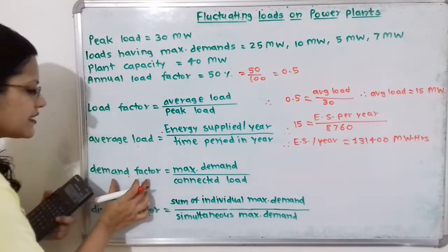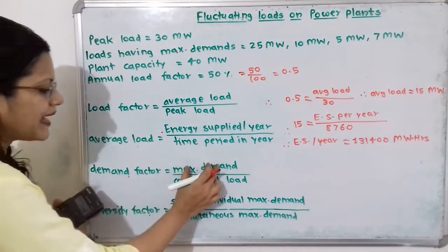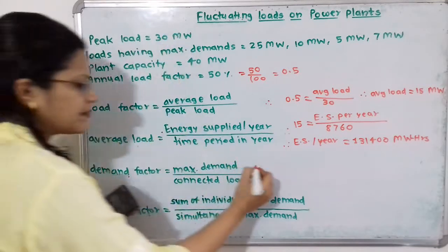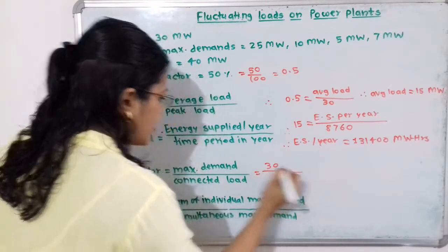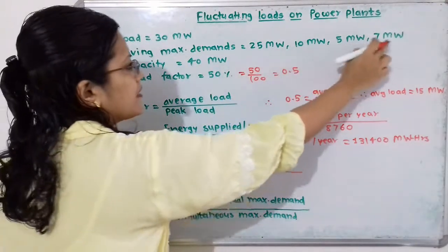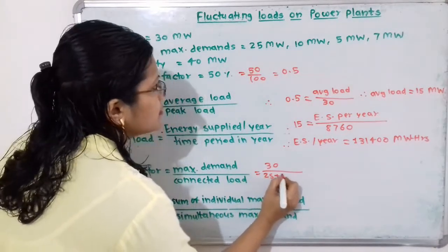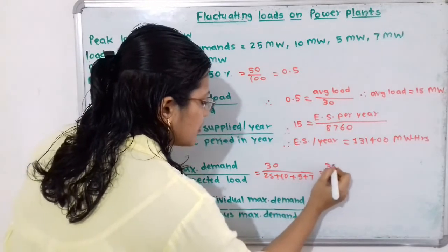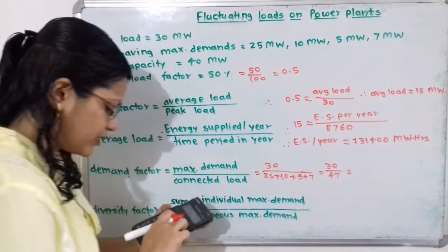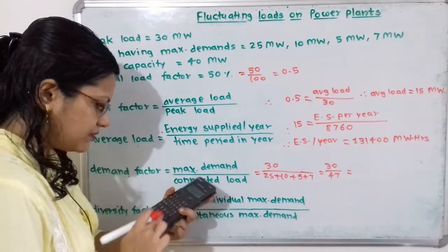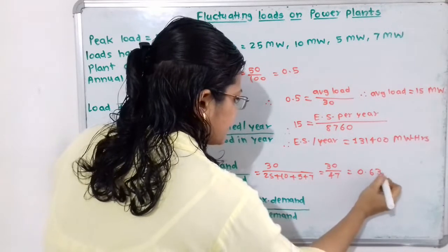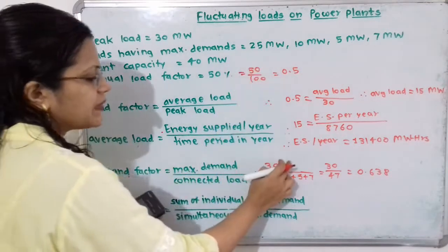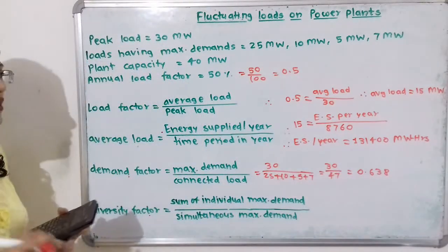Now we will calculate the demand factor. Demand factor equals maximum demand divided by connected load. Maximum demand is the peak load, that is 30 MW. Connected load is 25 plus 10 plus 5 plus 7, which equals 47 MW. So demand factor equals 30 divided by 47, which is 0.638. Both values are in MW, so the units cancel and there is no unit.